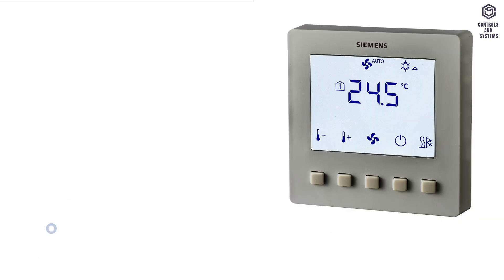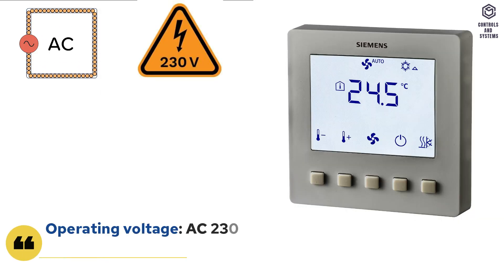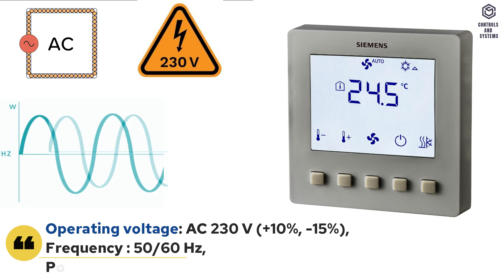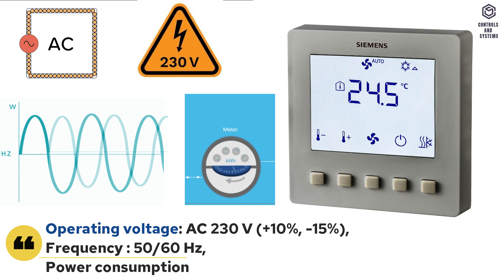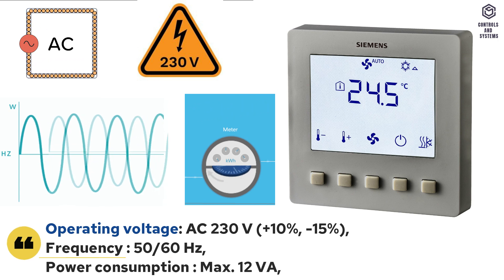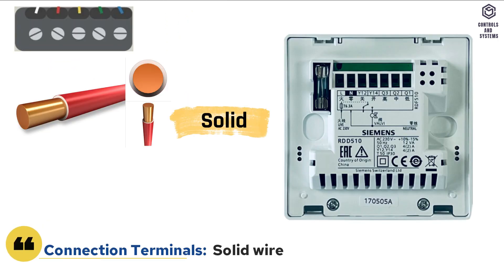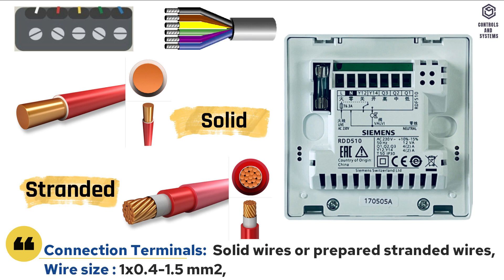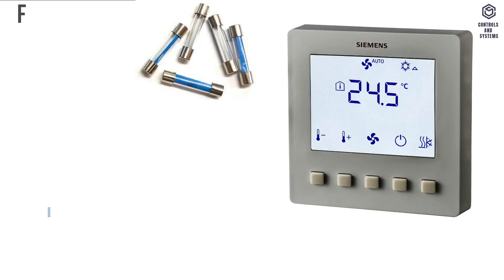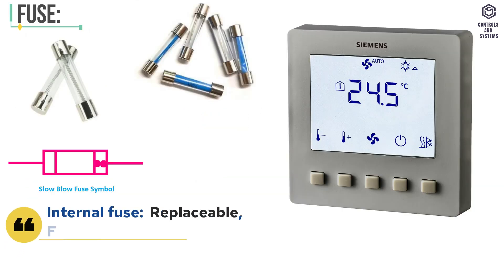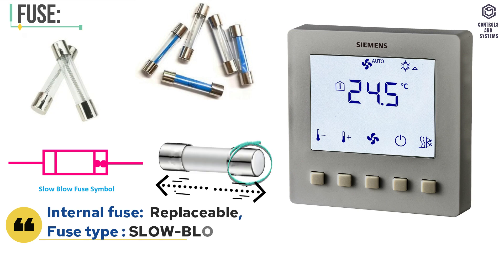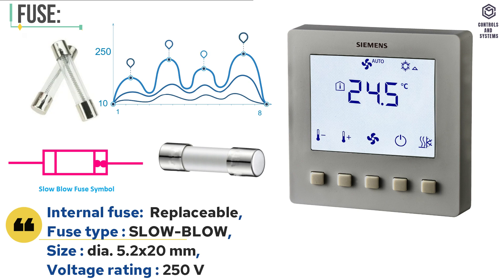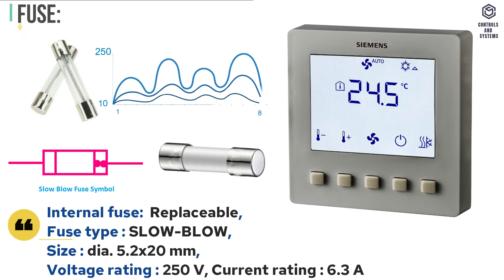Electrical data: operating voltage is AC 230 V (+10% / -15%), frequency is 50 or 60 Hz, and power consumption is maximum 12 VA. Connection terminals accept solid wires or prepared stranded wires, wire size 0.4 to 1.5 square millimeters. Fuse: internal fuse is replaceable, type slow-blow, size 5.2 × 20 mm, voltage rating 250 V, current rating 6.3 A.